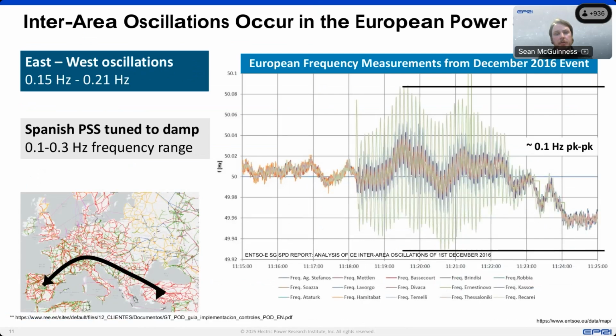Another topic which has been brought up quite a lot in relation to this event has been oscillations. They're very frequently mentioned in posts on LinkedIn, website news reports and so on. So a little bit of context there: there are a number of known oscillatory modes on the European grid, particularly the east-west oscillations, which tend to go from Spain over to Turkey. They're in that 0.15 to 0.21 hertz range, so relatively low frequency.